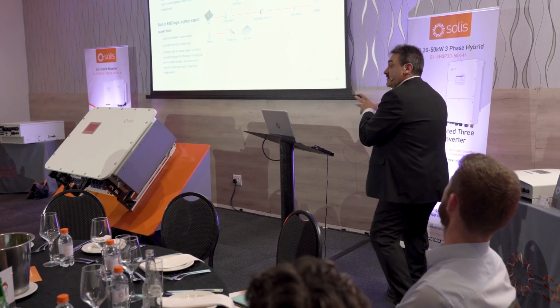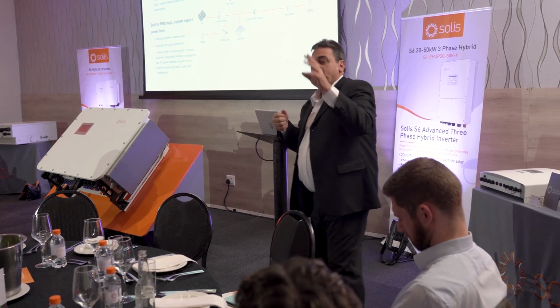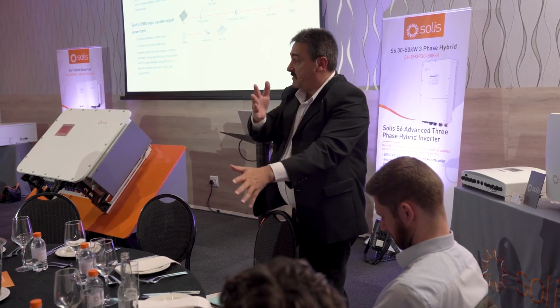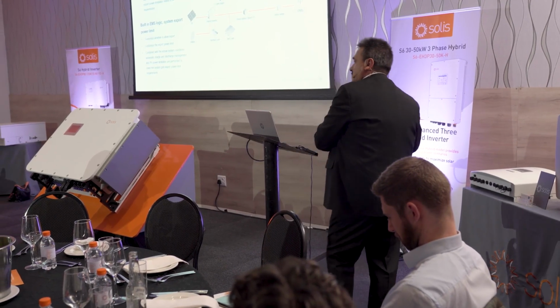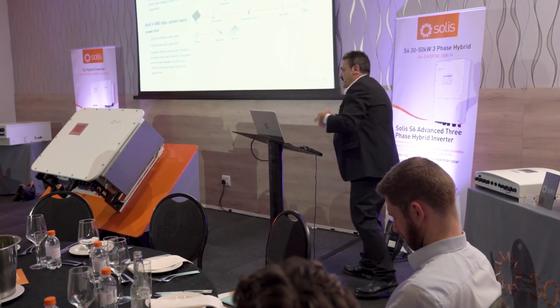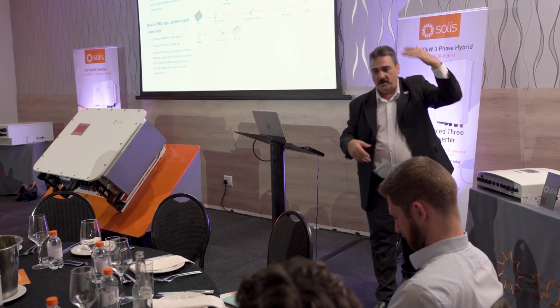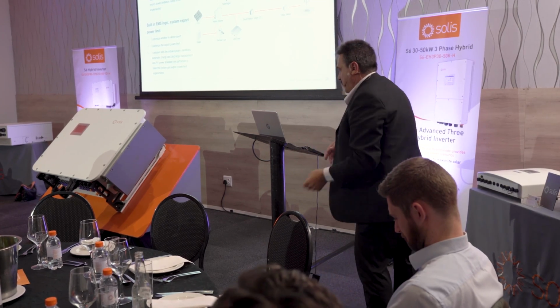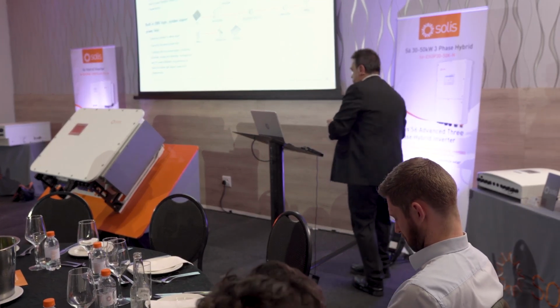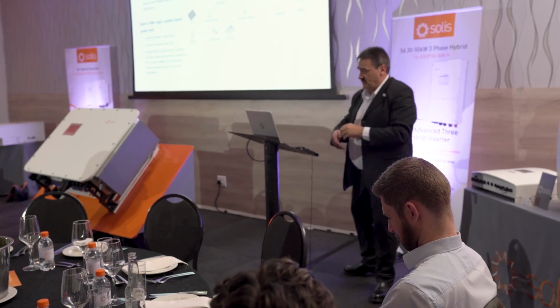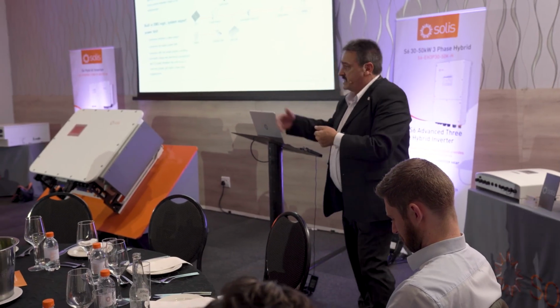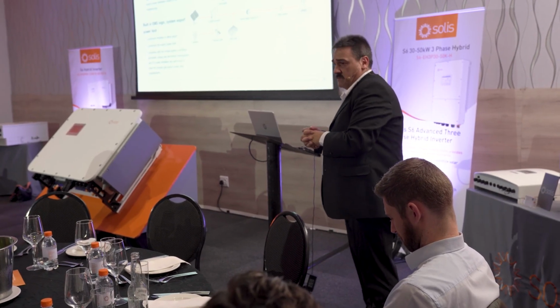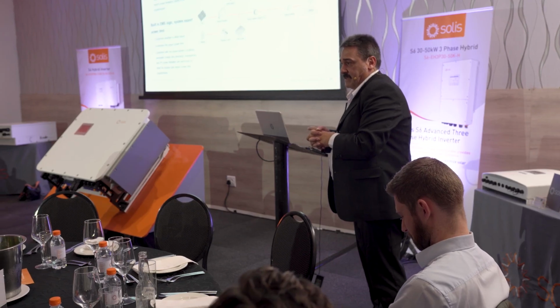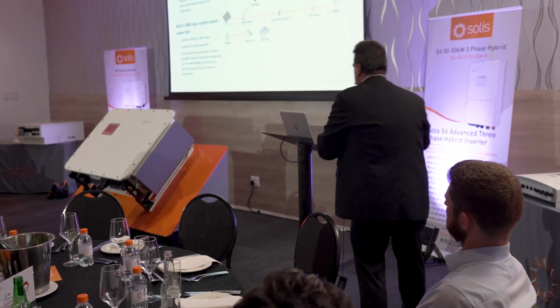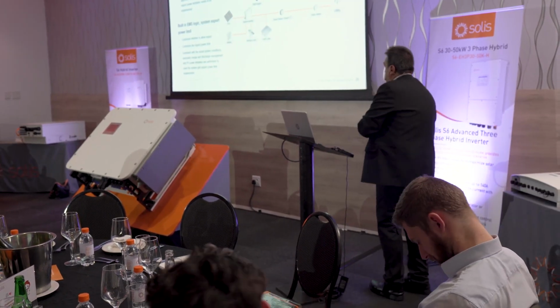You cannot go take from phase 2 and say, that red bus bar is full, here's some more power from the white one. In other words, what we're saying is phase 1 on the grid side can sit at 41 kilowatts, phase 2 can sit at 5, and phase 3 can sit at 0, and it will just handle it. Exactly the same applies to the backup board, which is quite a significant addition to the system.